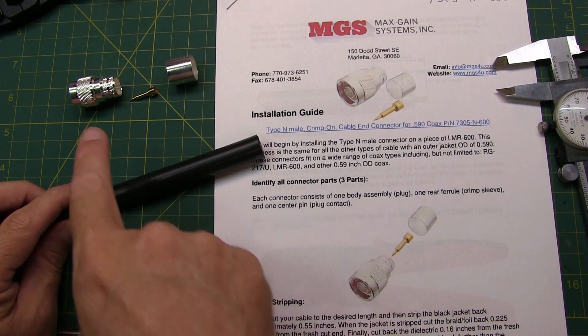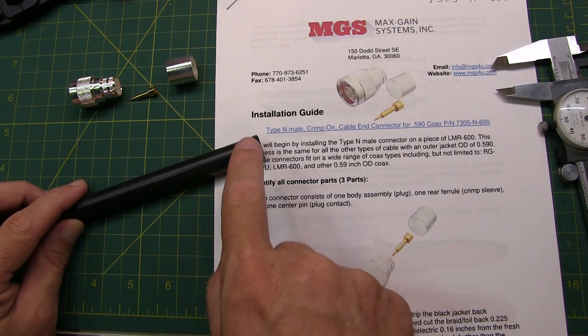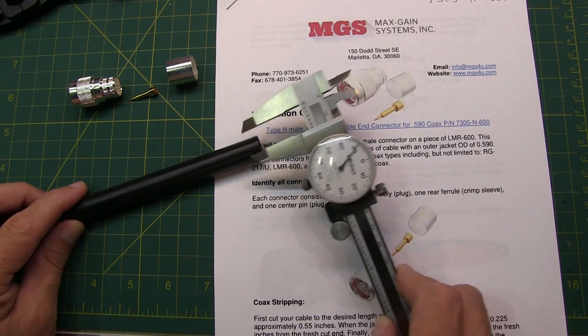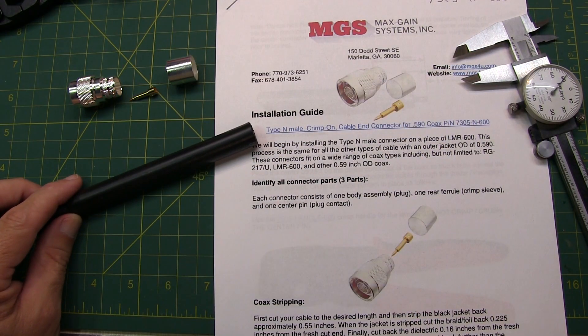This video is going to show how to install an N-male crimp-on style coaxial connector onto 0.59 inch diameter coax, such as LMR600 or RG217.